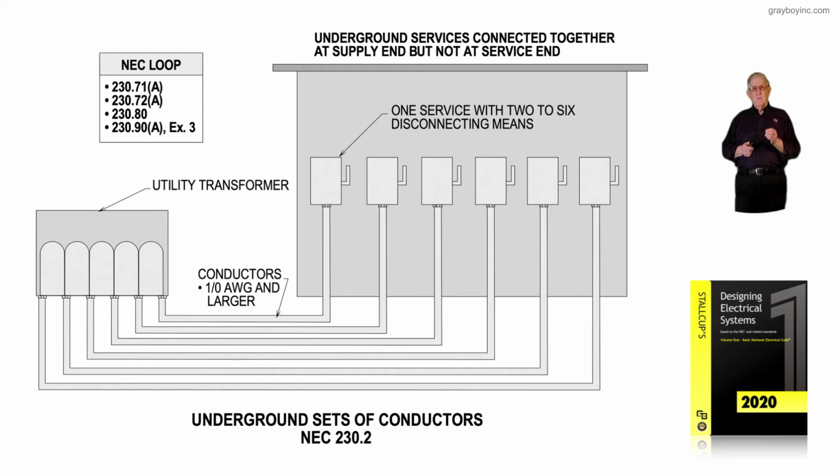Know where the service point is. So in this case, if we had a master meter out by the transformer and those runs went in and hit the disconnects and belong to the utility, then most of the time they have to be at least 2 foot deep, or maybe even a little deeper if they're over 1,000 volts, and maybe would even have to be encased with red concrete, or maybe a red ribbon put down to identify them as high voltage.